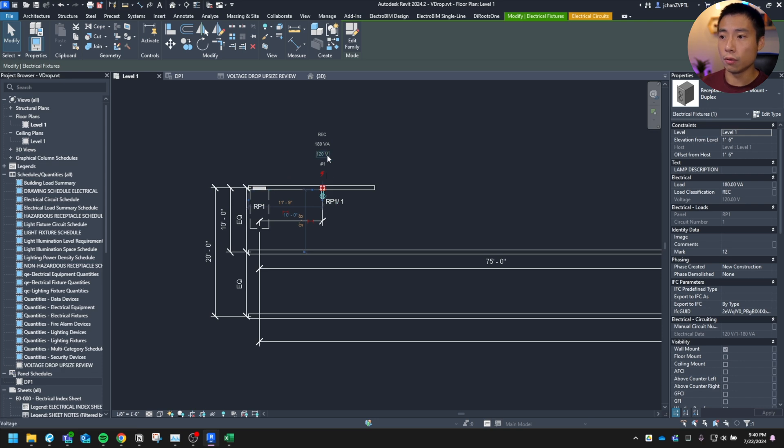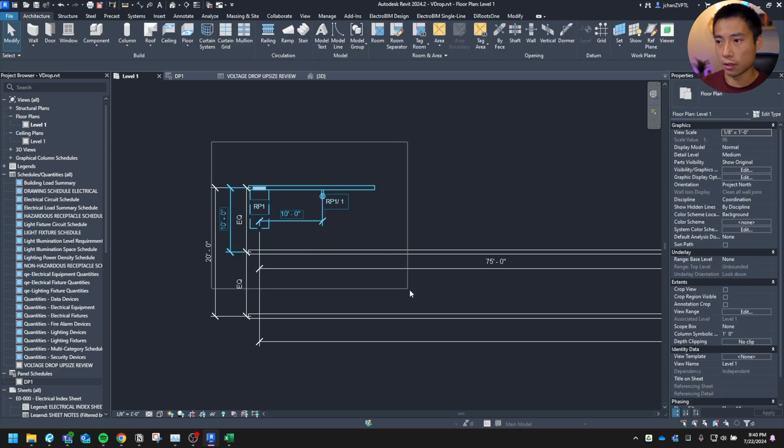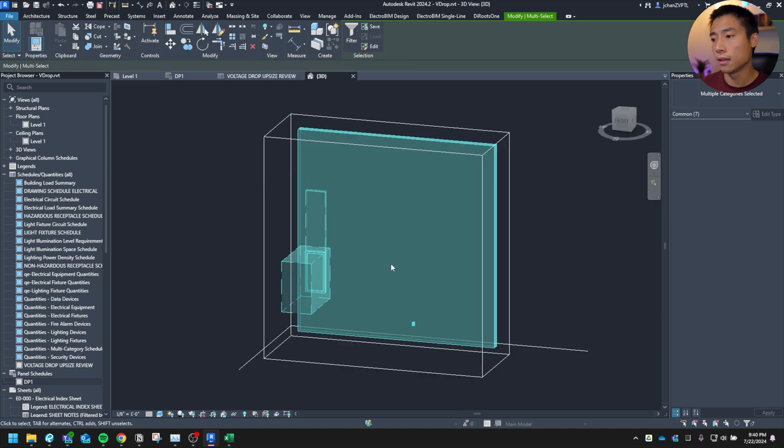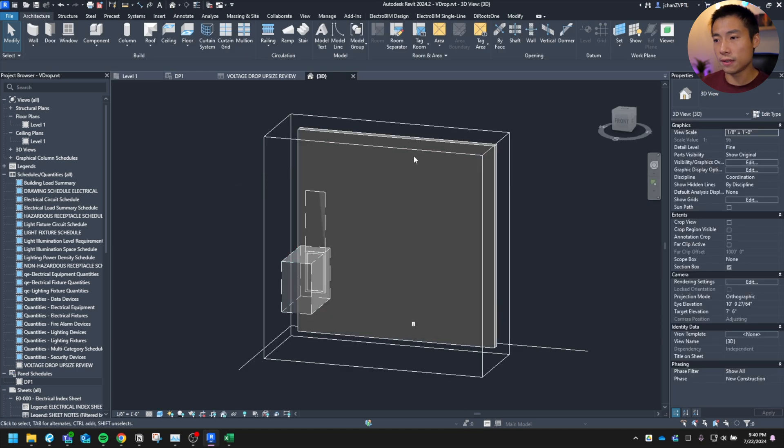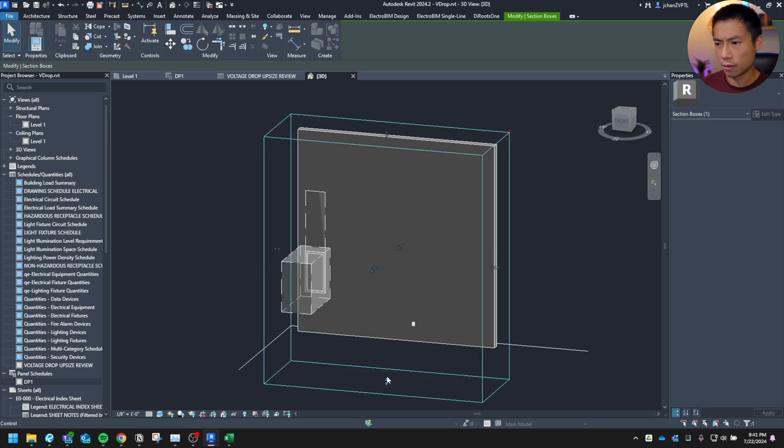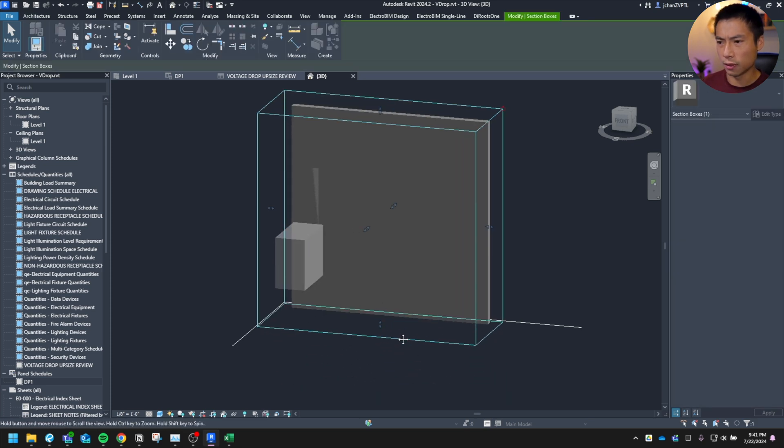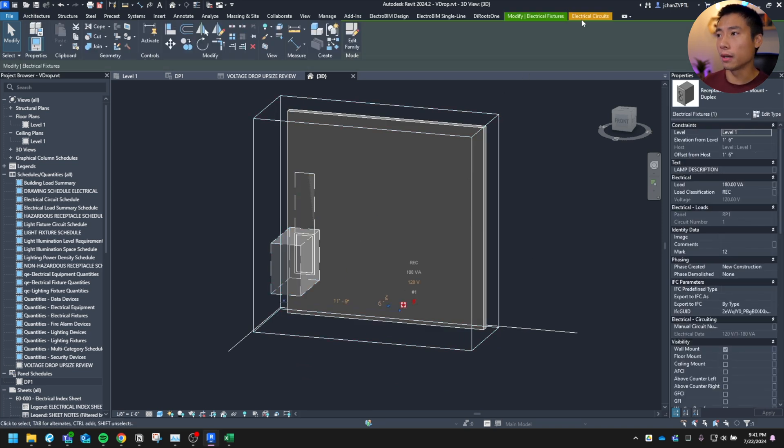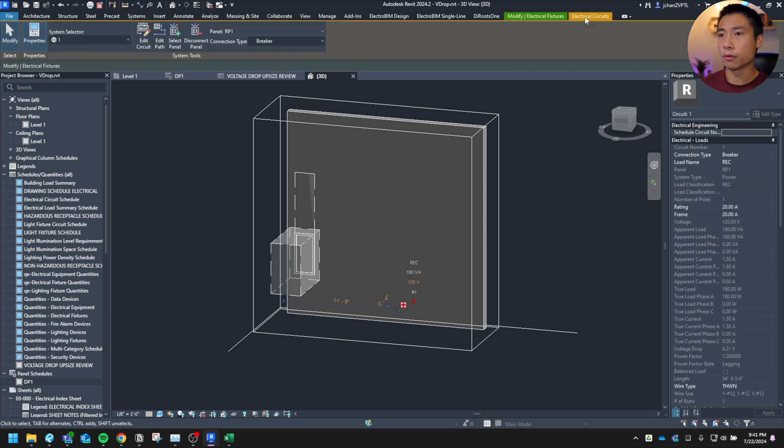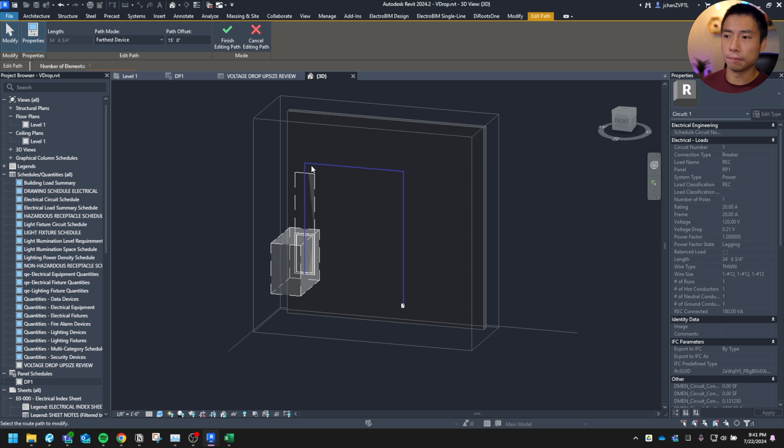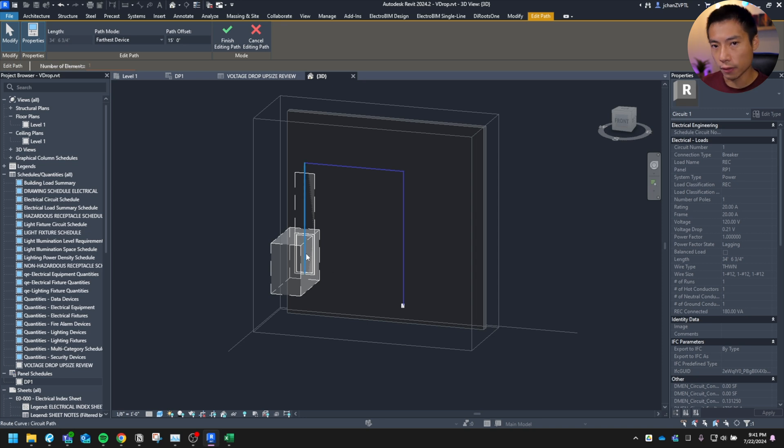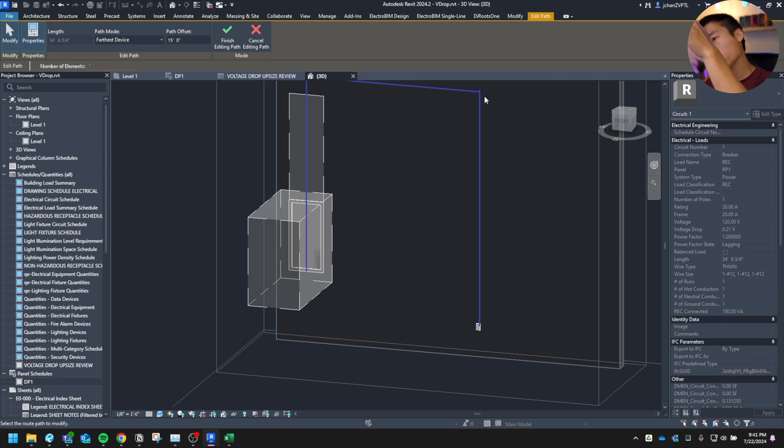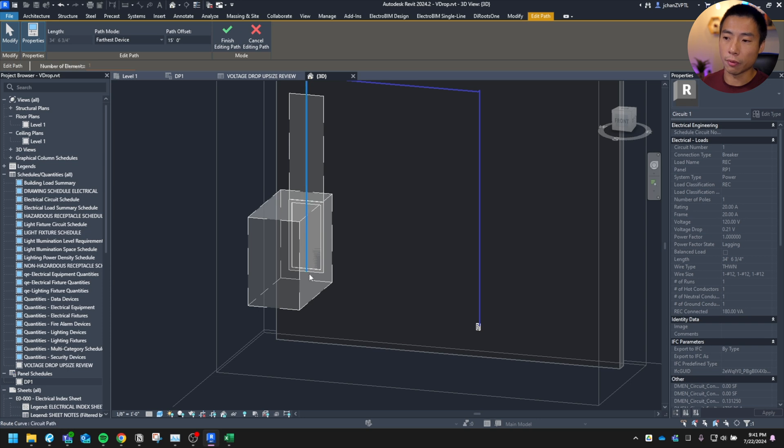So if you were to open up a 3D view, which is pretty simple, I just click this and then I hit the section box. So you can see how the panels in the wall, the receptacles in the wall. I think it looks a little off, but it's in the wall. And if you were to click on the receptacle and click electrical circuit and hit edit path. So once you hit edit path, you can see that it does try to figure out what the electrician is likely going to do in the field. So you see how it takes the worst case scenario. If it's going up into the ceiling space, going over and coming down the wall, it assumes that the circuit's going to come from the bottom of the panel. So that's worst case scenario.